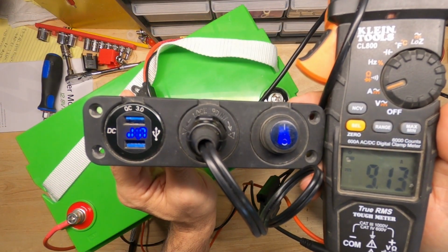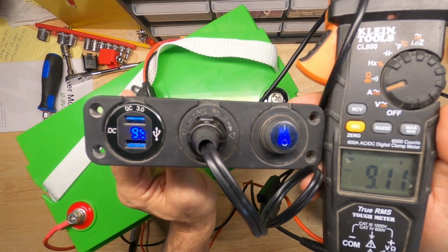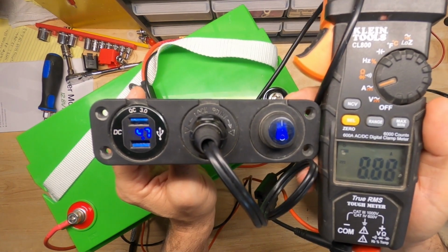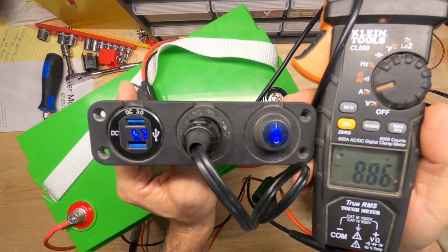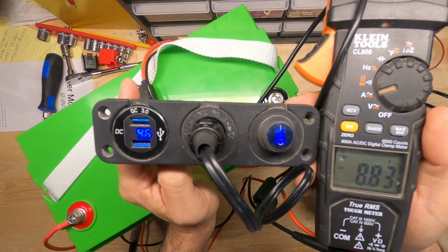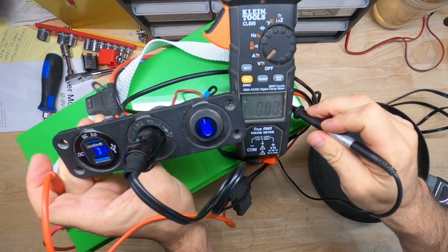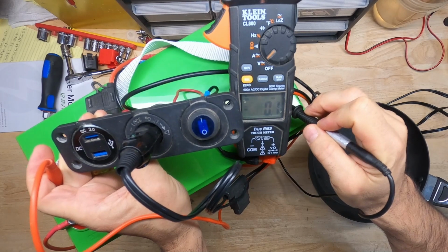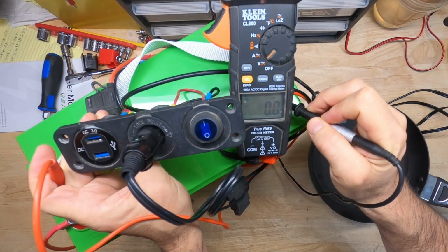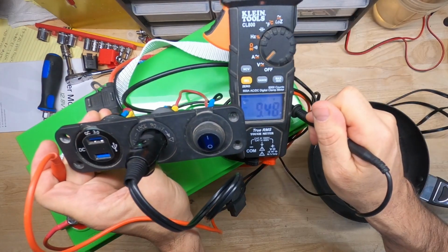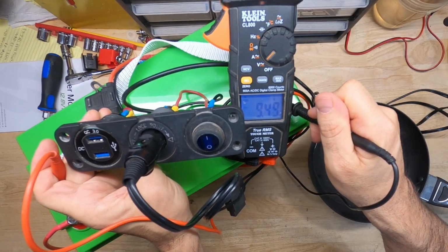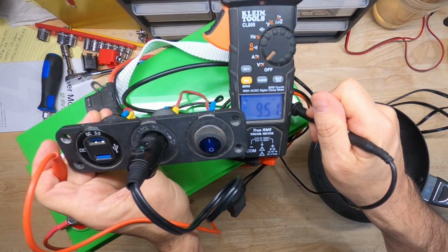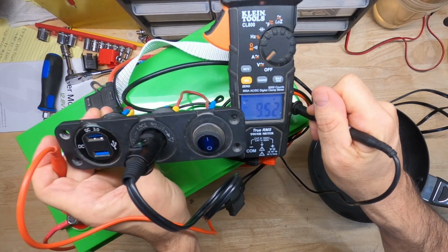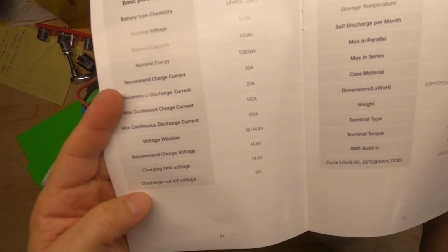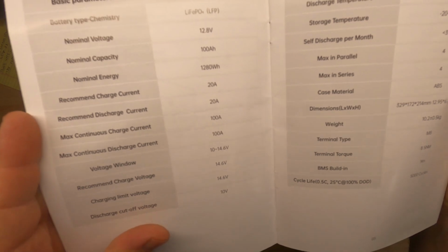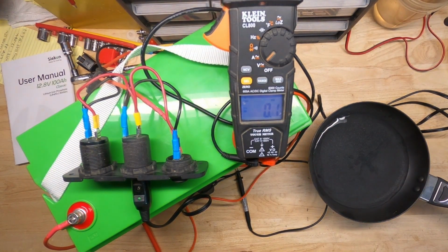This thing is going to the bitter end. It's giving it all she's got. 9.9. The reason for this discrepancy could be the internal voltage that the BMS sees versus this meter here. Oh, finally cut off, 9.62 on the meter. I barely cut it. See how long it takes. Oh, there, it's recovered already at 9.5 volts. So it's a little low. And per the manual, they have a discharge cutoff voltage of 10 volts. So it's off by about 0.4 volts.